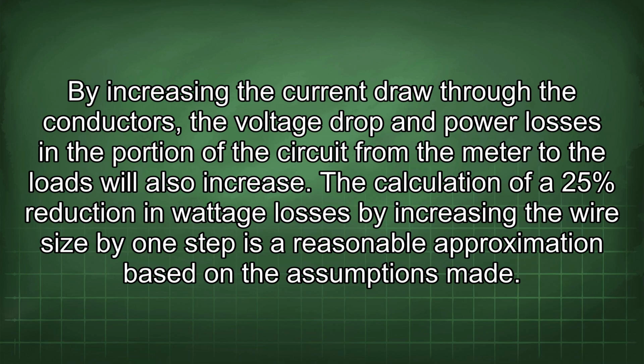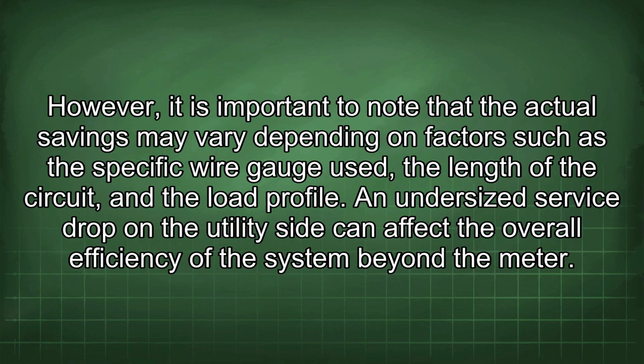The calculation of a 25% reduction in wattage losses by increasing the wire size by one step is a reasonable approximation based on the assumptions made. However, it is important to note that the actual savings may vary depending on factors such as the specific wire gauge used, the length of the circuit, and the load profile.